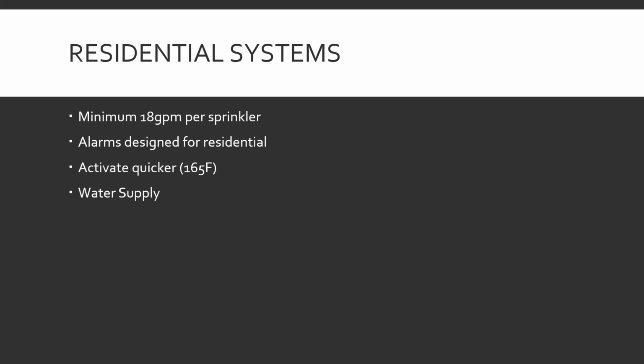Residential systems have a minimum of 18 gallons per minute per sprinkler. Little amount of water. Again, it's not some big fuel factory. You can get away with a small amount of water for a small amount of problem. The alarms are designed for residential purposes. A little simpler. Not all the bells and whistles of a big full-size system. It's a little easier to troubleshoot problems. Just in general, user-friendly for the average guy or whoever with it in their house.